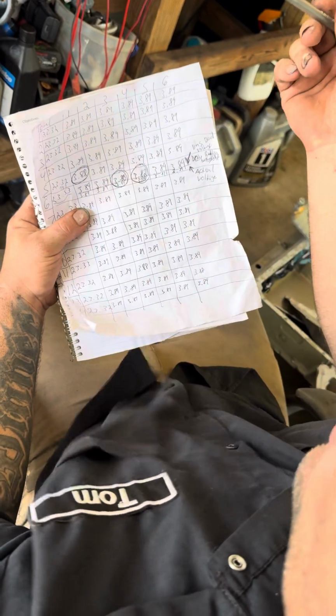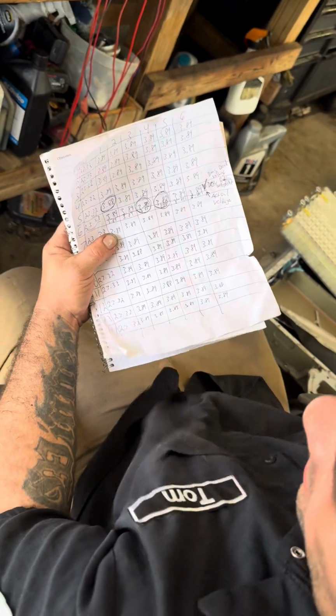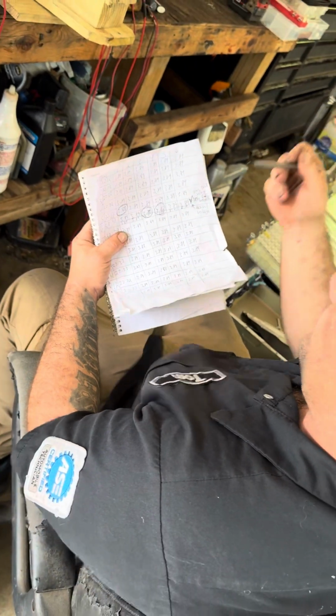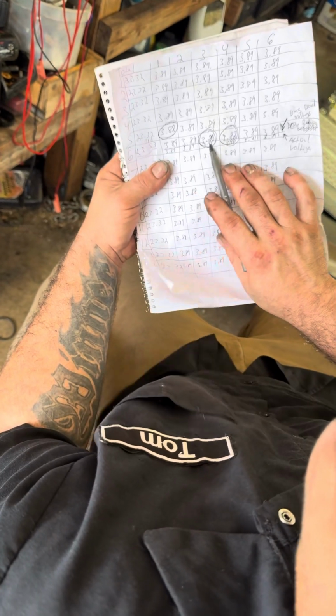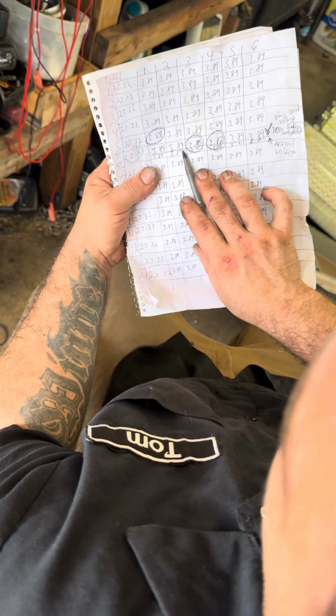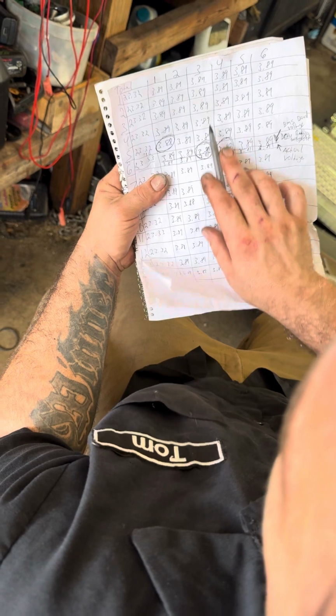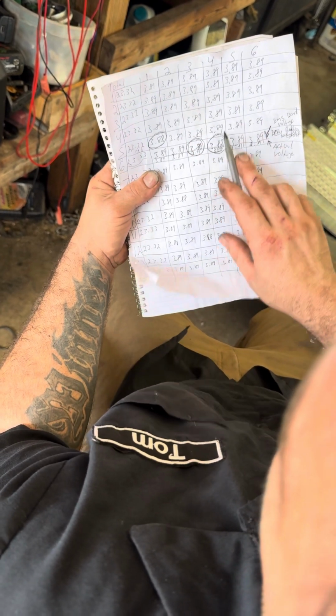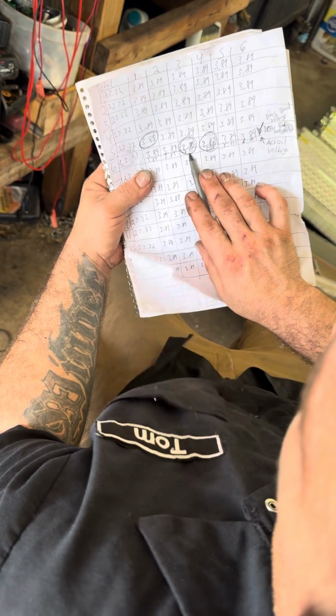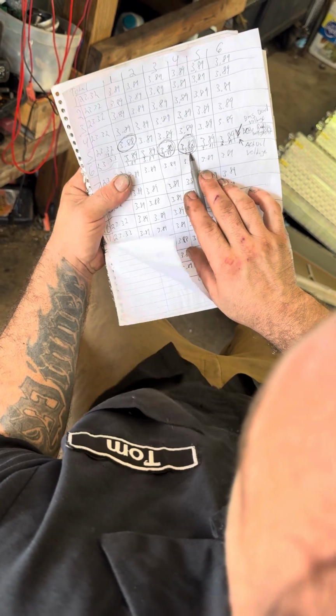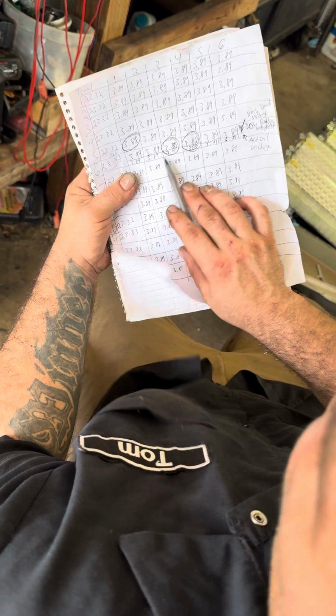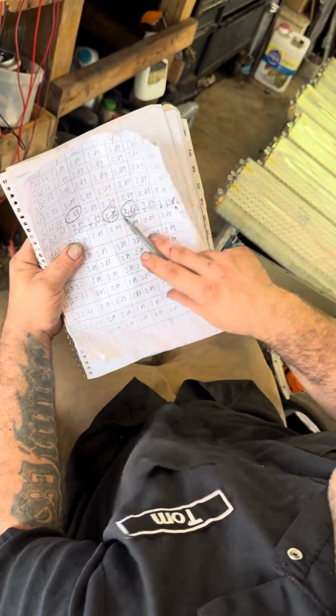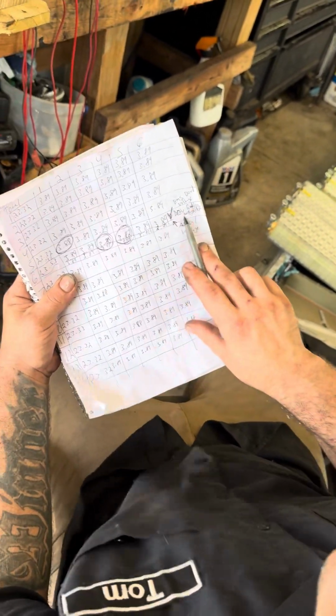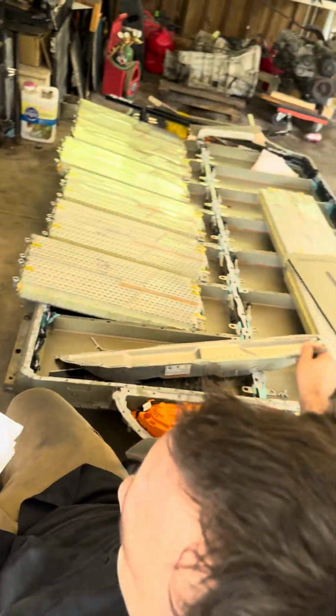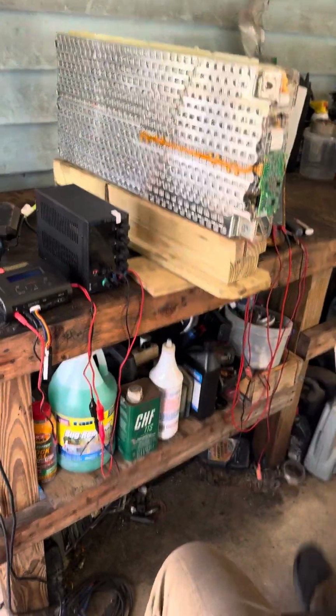So essentially the BMS board here is causing an imbalance. This BMS board is bad. You can see here on the top, these are the readings from the BMS board itself. And we have 3.80 on cell 3 and 3.82 on cell 4. But actual voltage readings are 3.99, 3.99. These are only allowed to be 0.2 difference from themselves. So the battery module would shut this off, and I'll show you how I found that out.